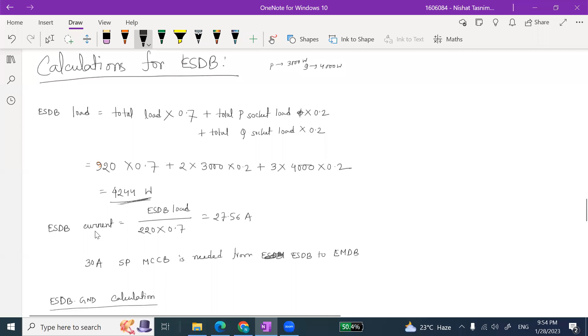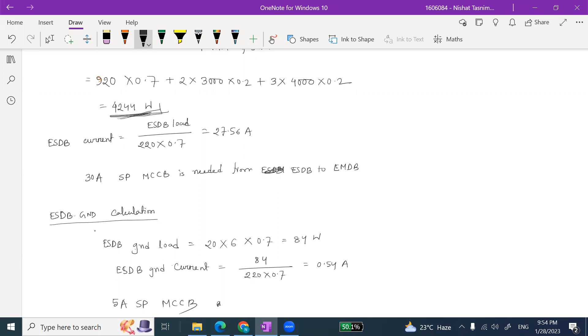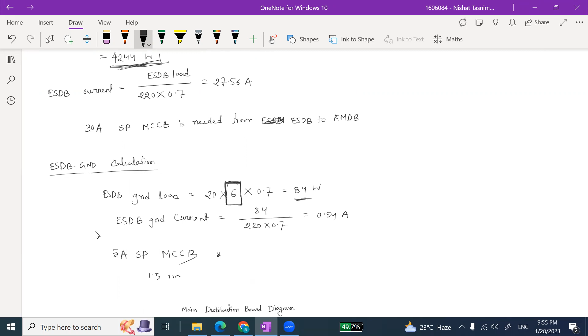Remember this: the 4244 watt was only for the ESDBs, not for the ESDB ground. So the ESDB ground load was 84 watt, right? 84. And we do not need to multiply it with 12, because we have already multiplied it with 6, since there are a total of 6 lights in 6 floors in the staircase area, right? So we can just write down 84 directly, or we can write 120 into 0.7.